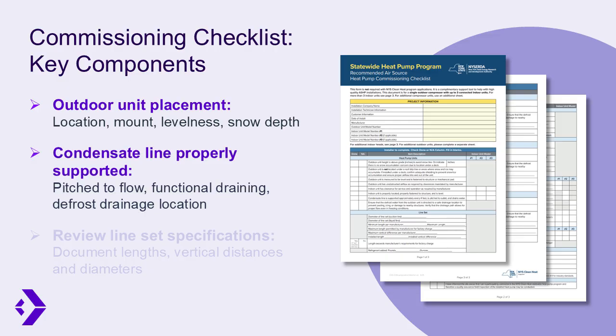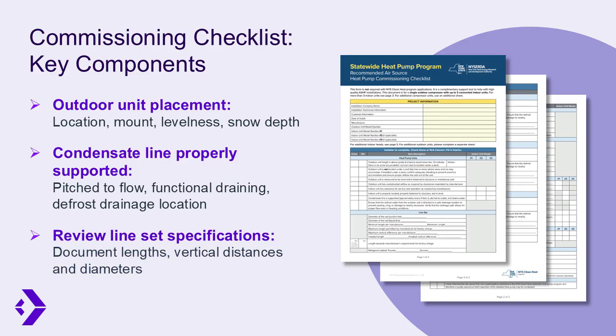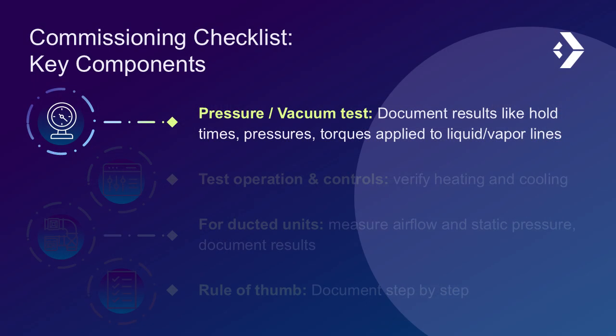Confirm that the condensate line is properly supported, pitched to flow to the outside or is assisted by a pump, and drains to an appropriate space. Also check the defrost drainage location and that the defrost strips won't cause a safety or functional issue if it refreezes after draining out. Next, review the line set specifications. Document the line lengths, vertical distances, and diameters of both the suction and liquid line. Confirm that the setup complies with manufacturer guidelines.